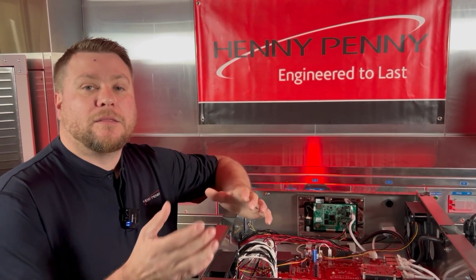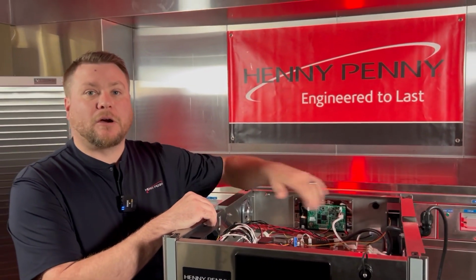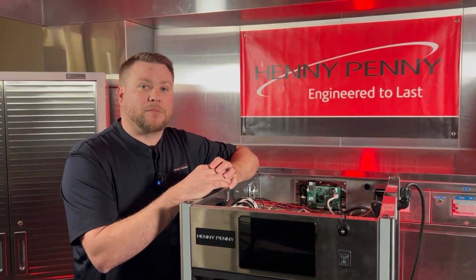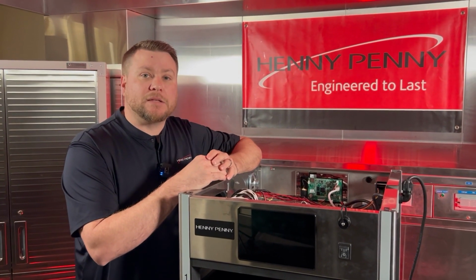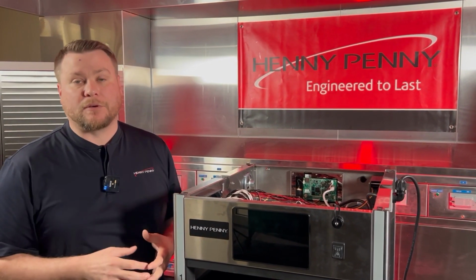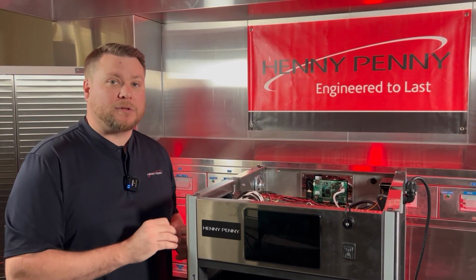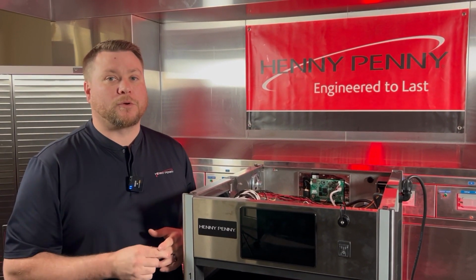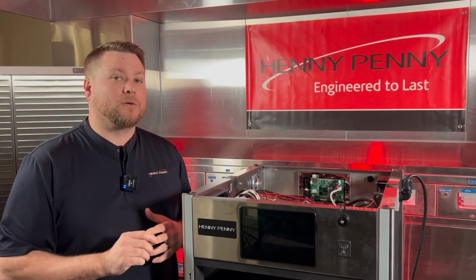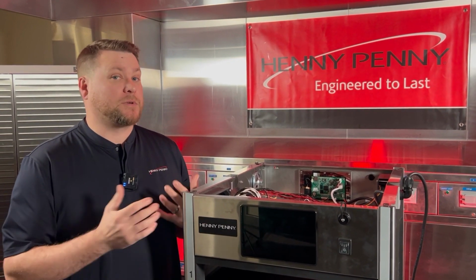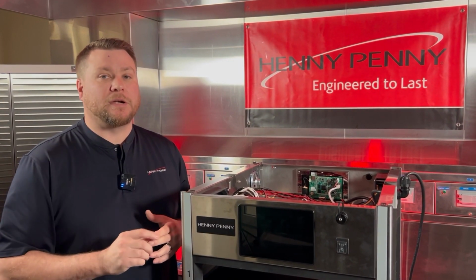And then the last thing is actually going to be our ambient air temperature probe up here. Remember, that is built into the I/O board and is not a replaceable item separately - it would require an I/O board replacement. So that's where the I/O board would come into play as far as a replaceable part within this error code.